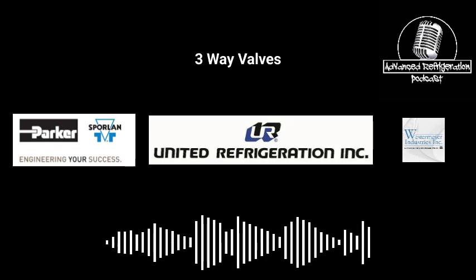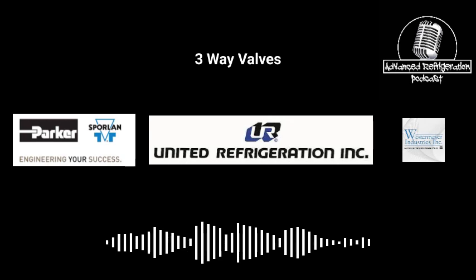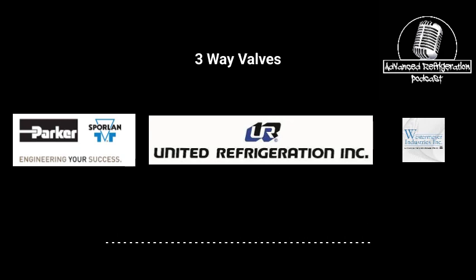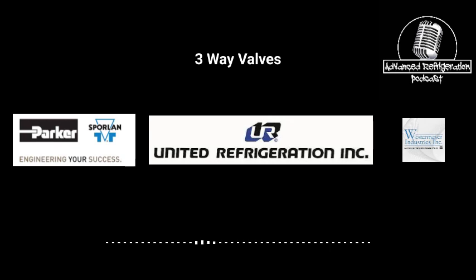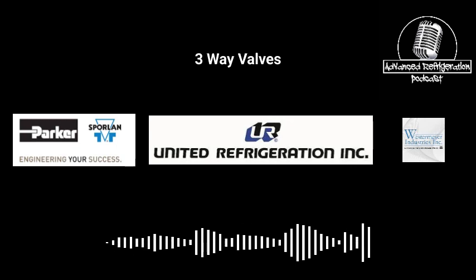Well, the three-way valve with the heat reclaim valves, we've had a couple where they just shifted in the middle and got stuck, and that's a nightmare. That's where you start running into head pressure issues and stuff tripping out because it's stuck. The piston is stuck between port A and port B, and you've got barely any gas going to either one, and that's a problem. Generally, when that happens, you can hear it.